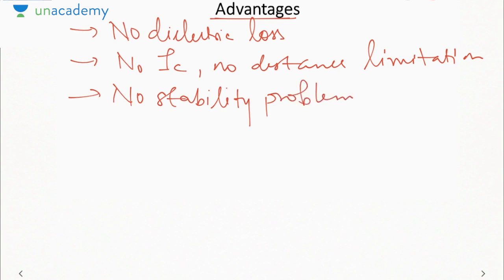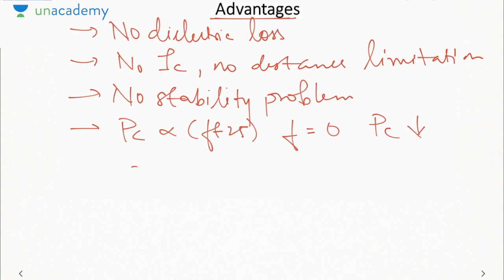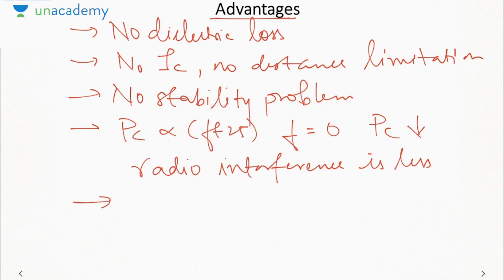Okay. Then, since we saw corona loss is proportional to (f + 25), here f is 0, so corona loss is less. If corona is less, radio interference will also be less, because corona causes radio interference as it induces third harmonics. So radio interference is less. Then, what is the other advantage? All these advantages will only work for larger distances, and the last advantage is that no compensation is required.